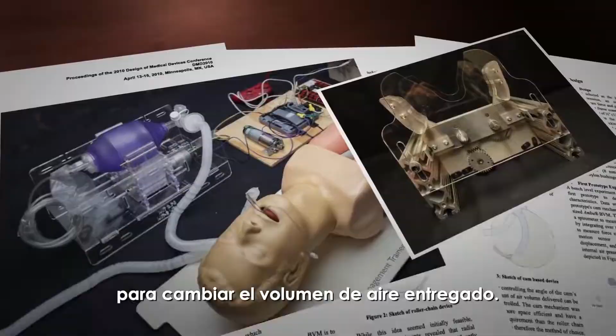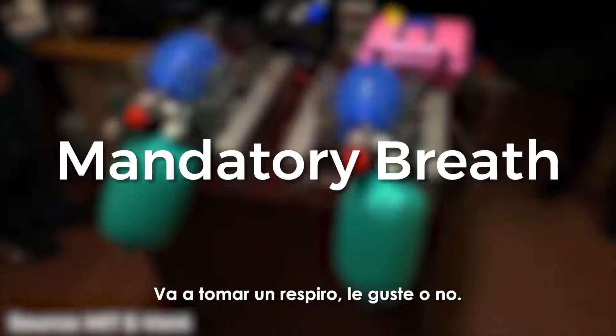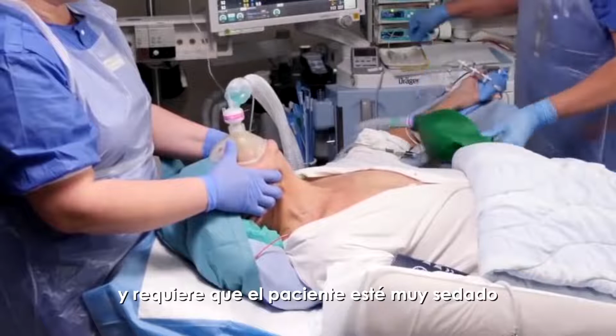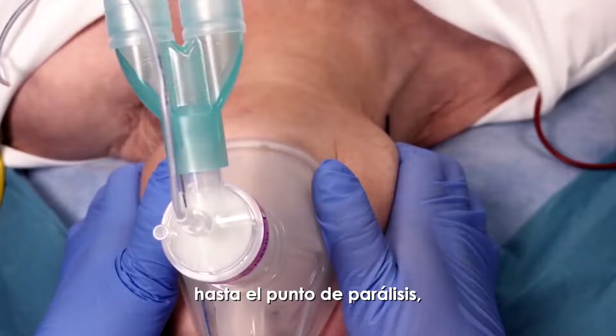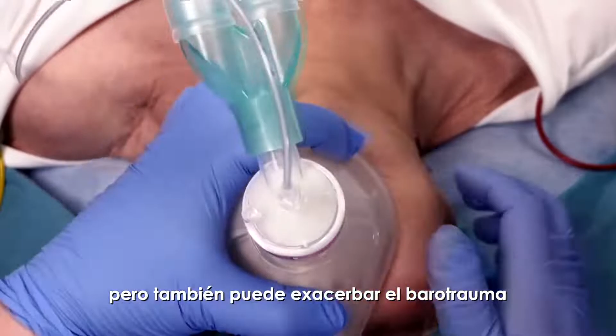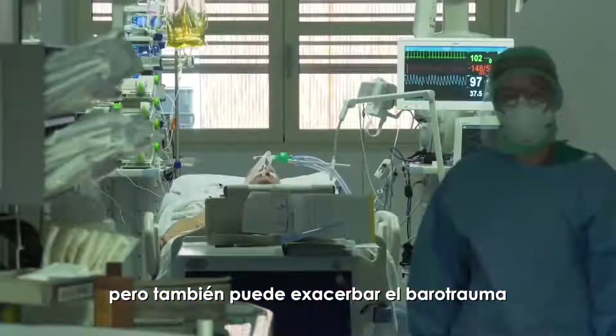This is a better design and may be useful in a do or die situation, but it is not perfect. The breaths per minute controller is simply set on a time-based frequency ranging from 5 to 30 breaths per minute. This is called a mandatory breath. It's entirely determined by the machine. You will take a breath whether you like it or not. This would obviously be uncomfortable and requires the patient to be heavily sedated to the point of paralysis. But it can also exacerbate barotrauma if the patient's diaphragm and intercostal muscles are resisting the inhalation.